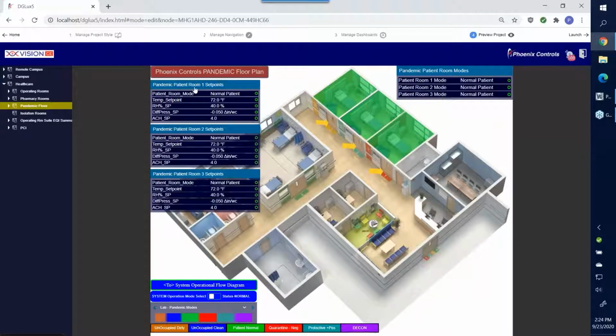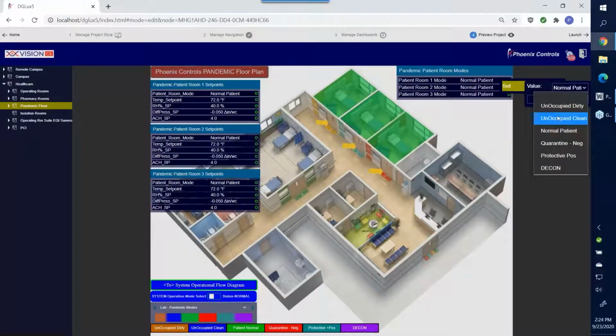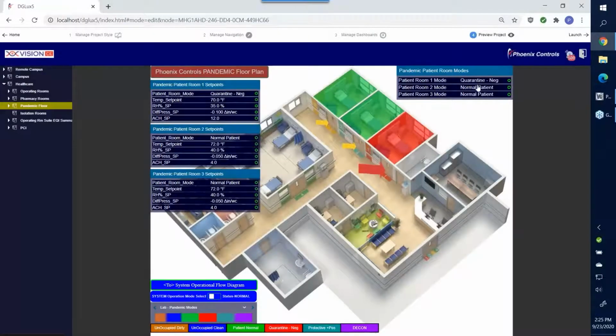So in addition to these modes, which we'll get into, you have all of the patient information shown here. Now, what's interesting is you'll see that right now we're running these rooms with an air change rate set point of 4, because they're all at the same temperature set point of 72. Now, obviously, if we're running in any kind of other mode that requires high levels of isolation, we don't have the time to train nurses or facilities people who haven't looked at this in 5 years how to do it. So the idea is very simply, I'm going to change these all into an isolated mode. And I'm going to do that essentially with just a click of a button and say we're going to make these quarantines. And then I'm going to change mode 1, so that's a quarantine.